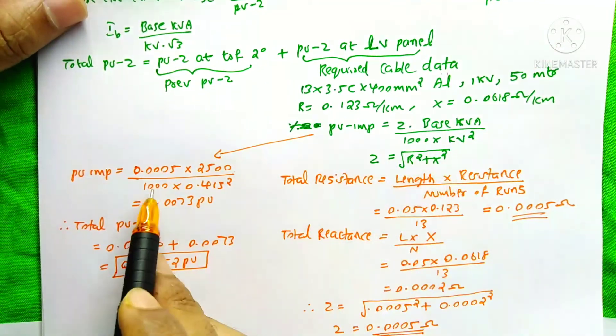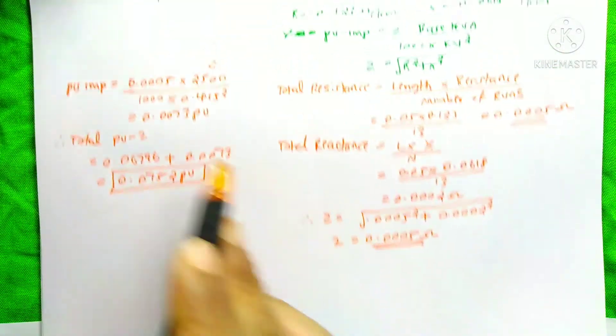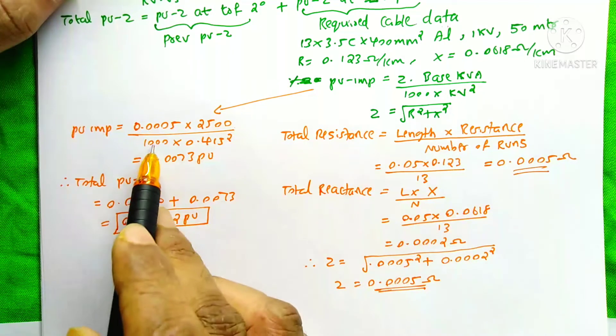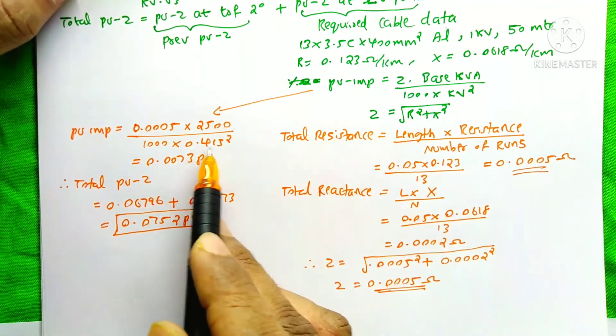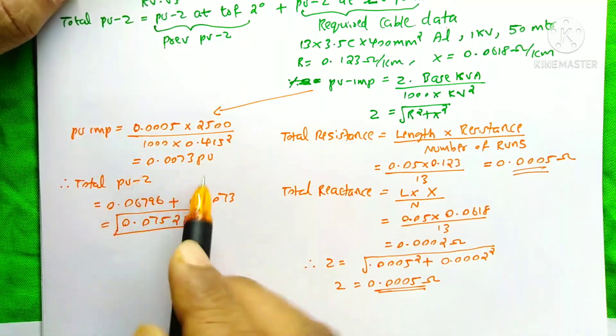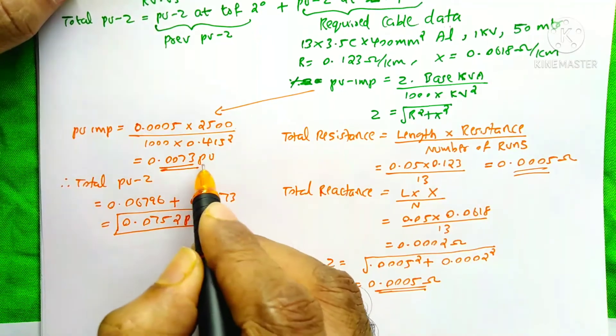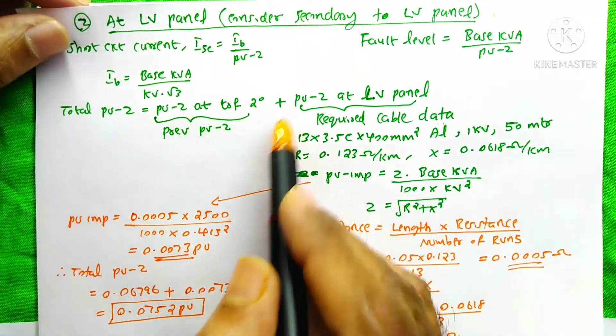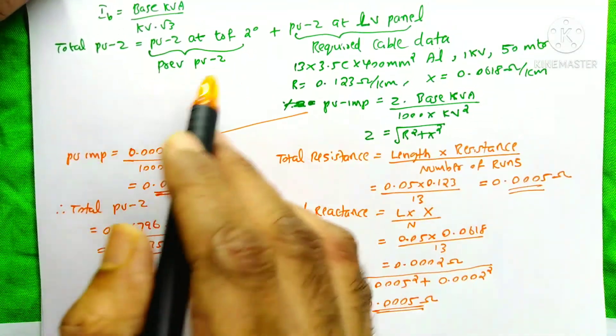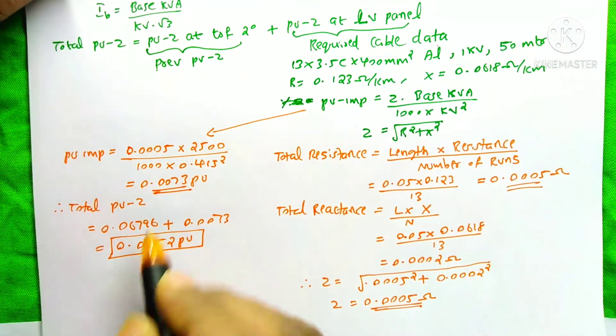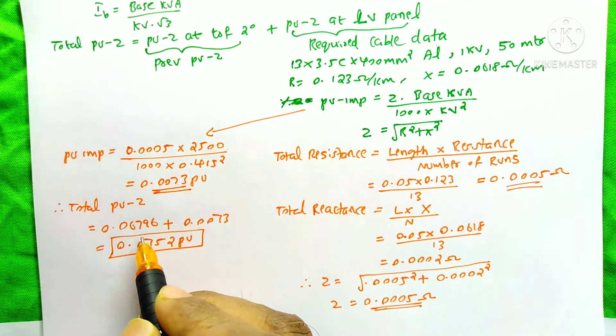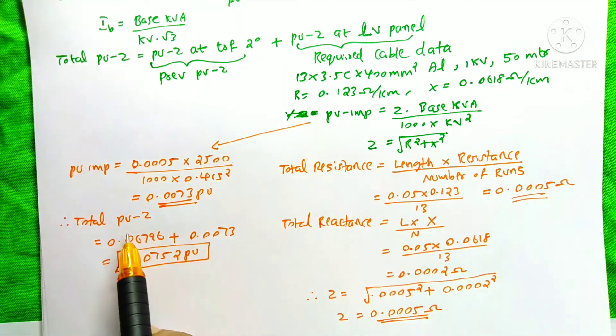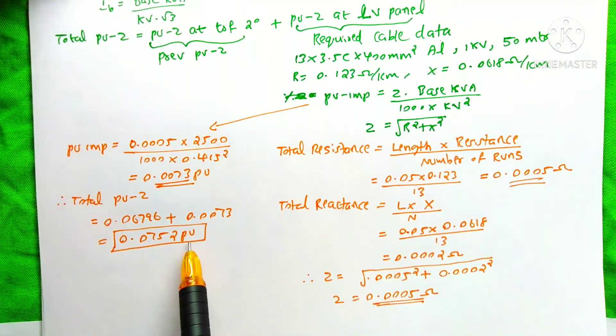Substituting: Z of 0.0005 into base kVA of 2500 kVA divided by 1000 into 0.415 squared. The answer is 0.0073 per unit impedance at the LV panel. So the total per unit impedance is the previous secondary value of 0.06796 plus 0.0073, giving a total per unit impedance of 0.0752.